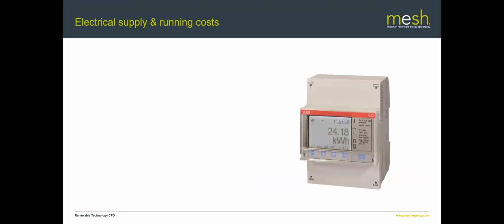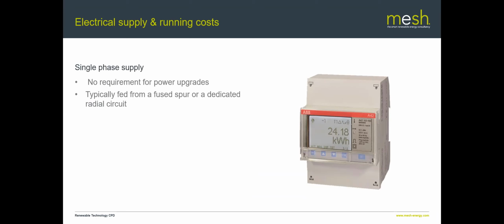So in terms of electrical supply and running costs, it's not really an awful lot to report. You're only talking about 100 watts or so. So generally speaking, you just feed the MVHR unit off a little fuse spur, or potentially a dedicated radial circuit. But you're not talking about more than 3-4 amps, absolute maximum. So you shouldn't worry about it too much. It is low running costs. You're not talking about putting a whacking great electrical device on your bill.